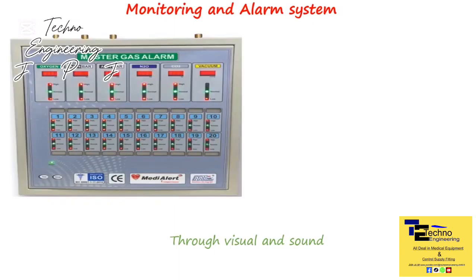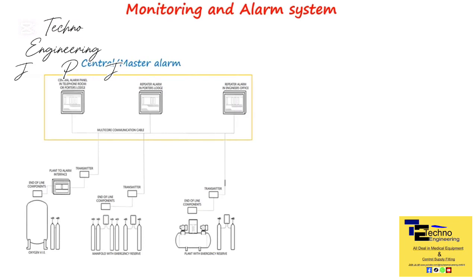For the safe and smooth operation of a medical gas pipeline system, a warning and alarm system is vital. This system uses visual indicators to show normal function and gives both visual and audible warnings in abnormal conditions. It comprises master and local alarms. The master or central alarm panel is located close to the medical gas supply source, such as the cylinder manifold or liquid oxygen storage tank.